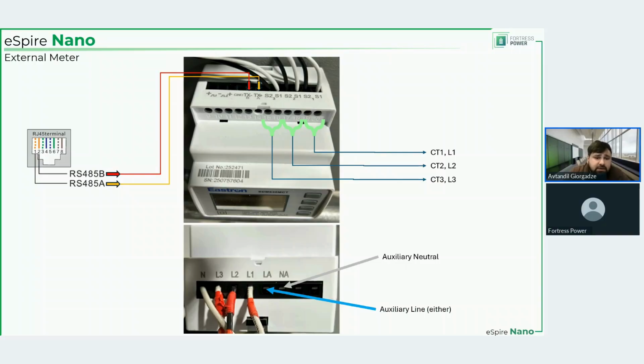You have auxiliary neutral, NA, and auxiliary line, LA. The reason why it says either in parentheses is because you can use L1, L2, or L3 by itself. The reference cables L1, L2, and L3 and the neutral will not activate the system. It needs auxiliary line and auxiliary neutral.